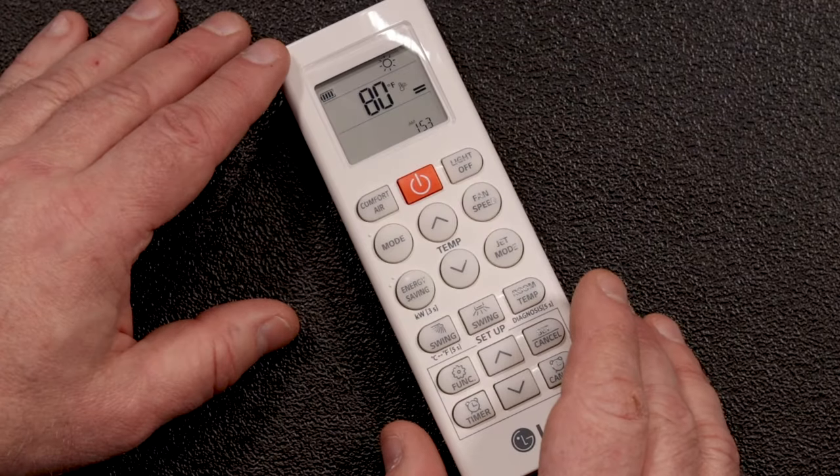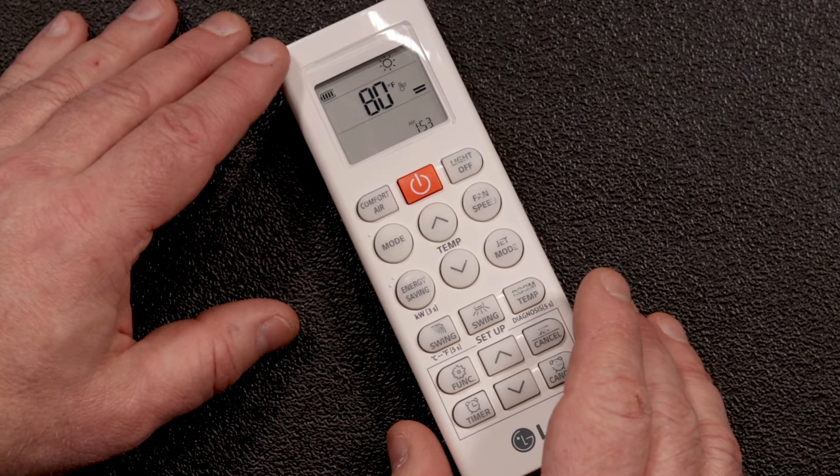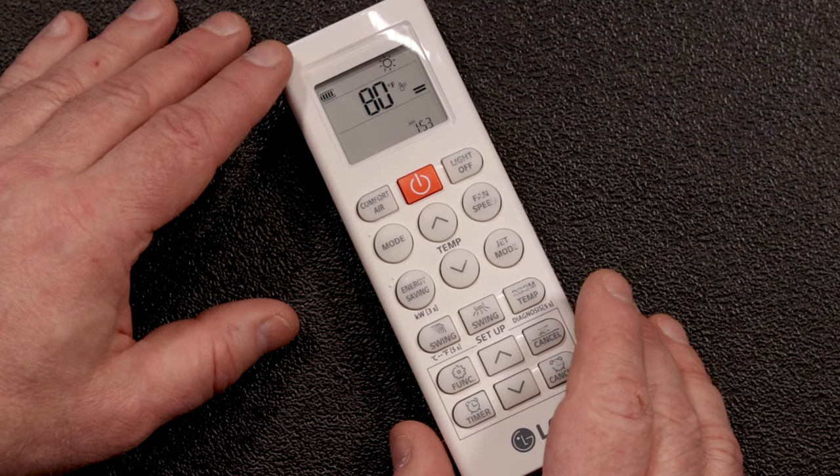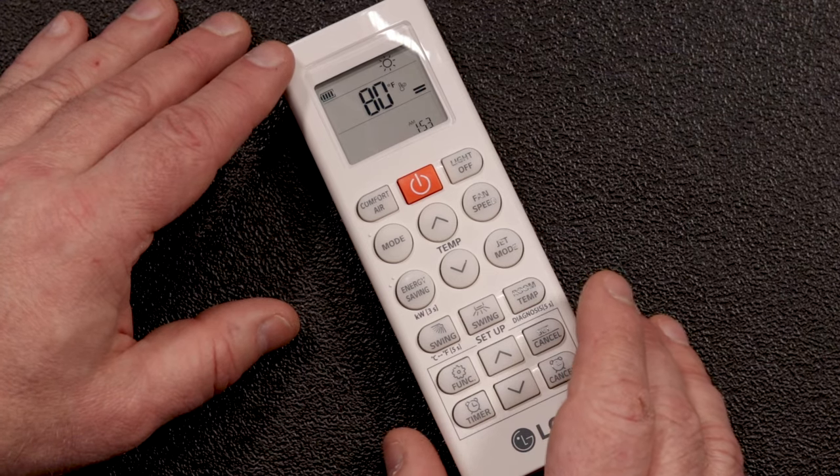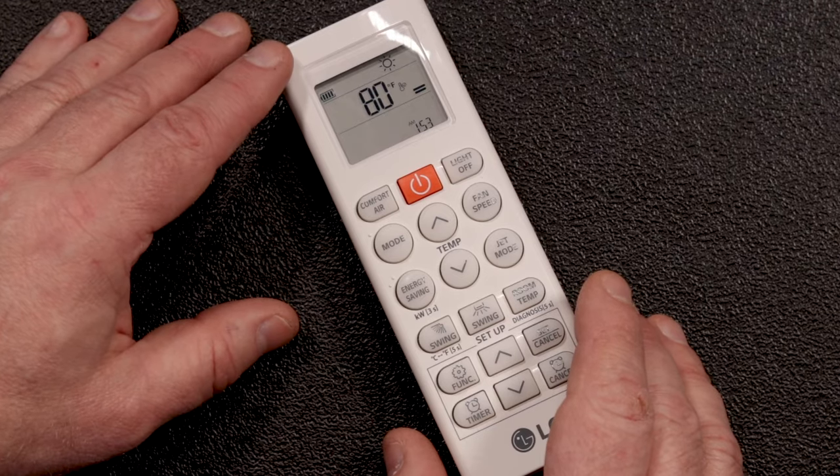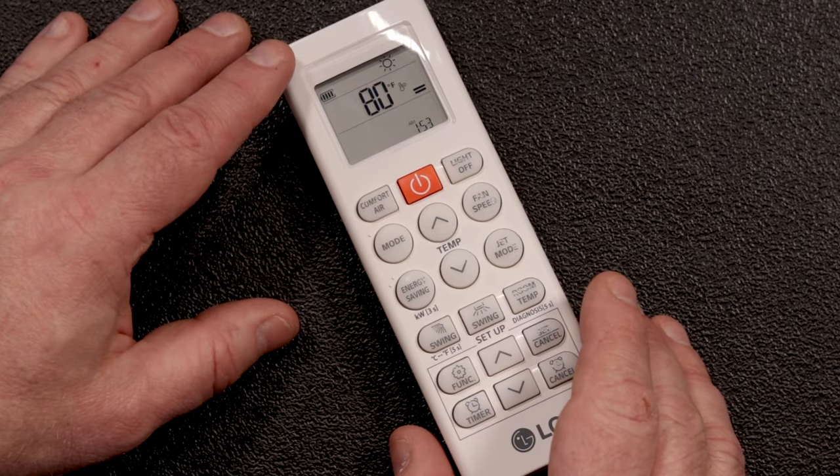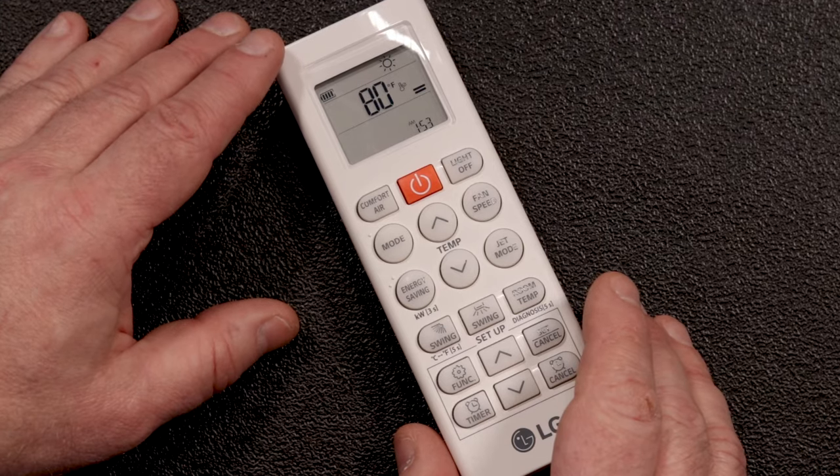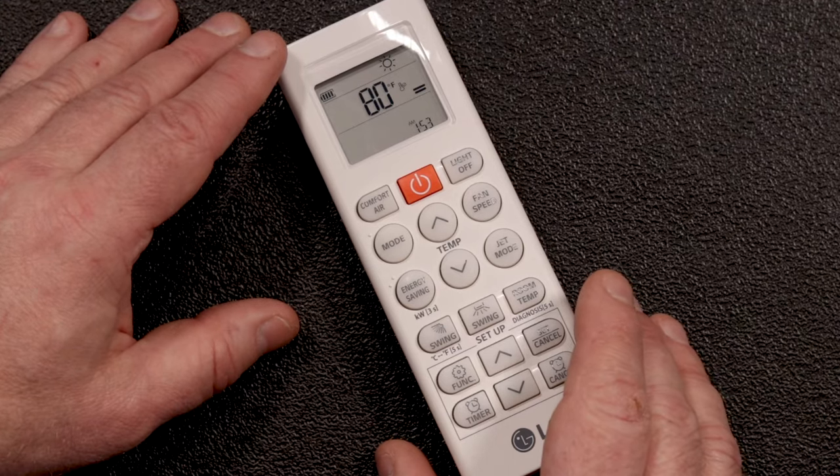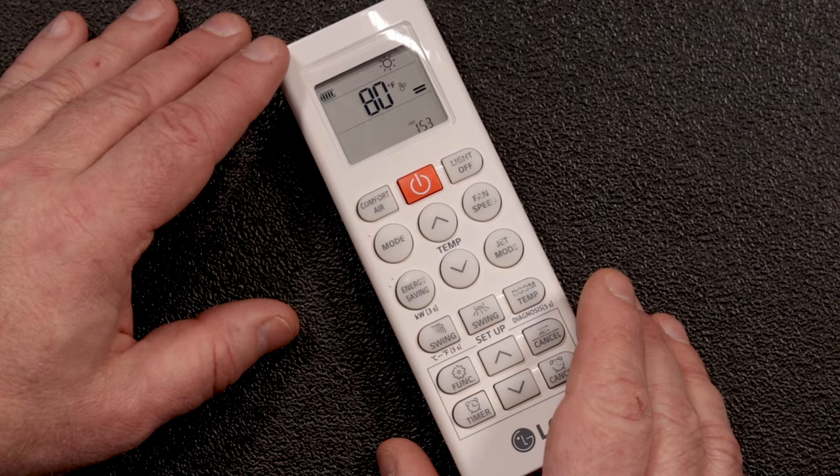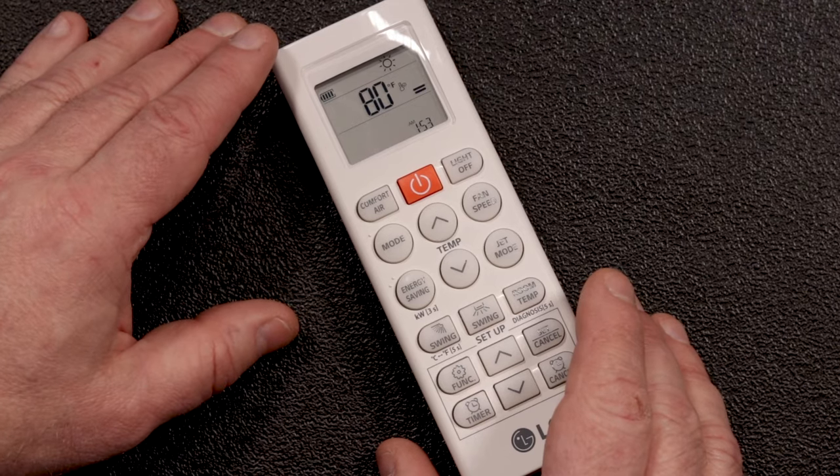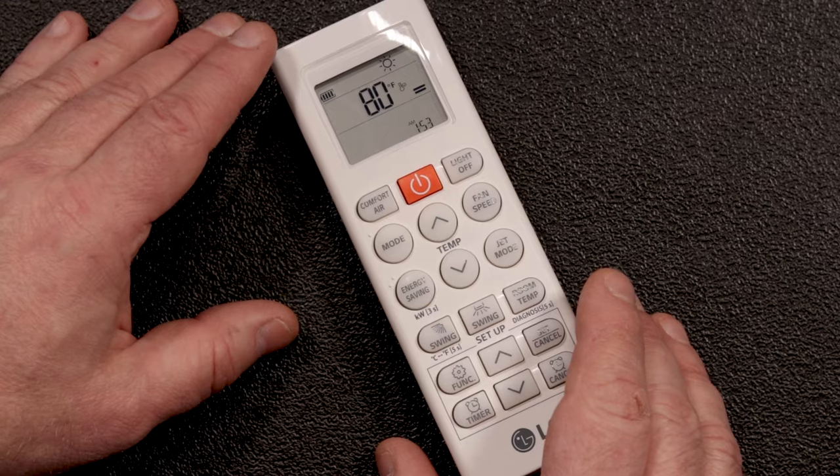One important thing to remember is that if you have multiple indoor heads connected to a single outdoor unit, you can't have some in heat mode and some in cool or dry mode. This will cause the system to shut down. You can mix heat, fan, and off modes. You can also mix cool, dry, fan, and off modes. But you can't put the system in a configuration where it's trying to heat and cool or dry at the same time. This problem usually comes up in the fall when people turn on their heat for the first time, and in summer when folks first turn on their air conditioning.